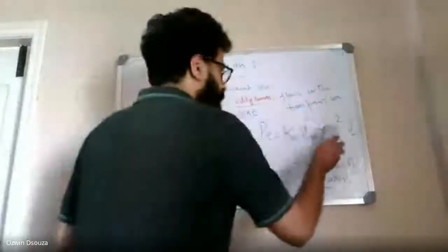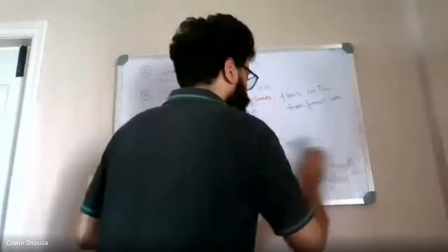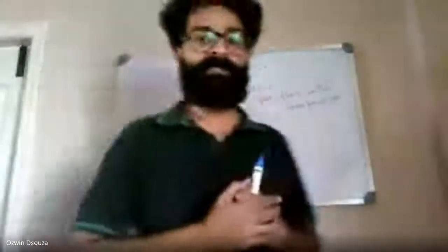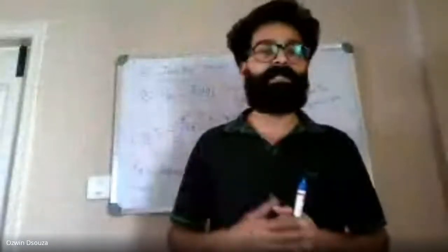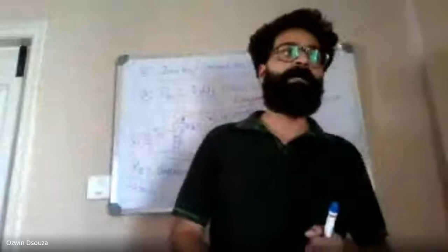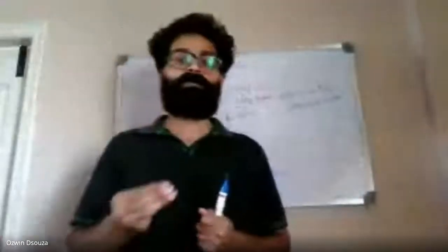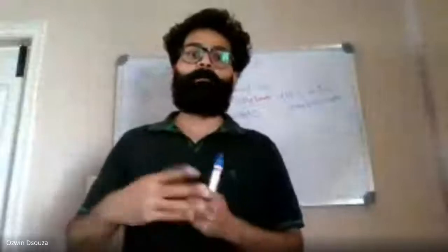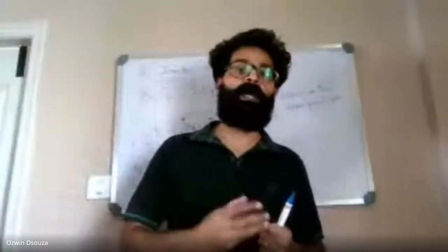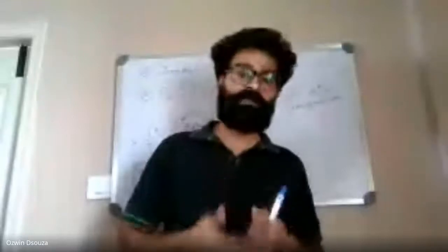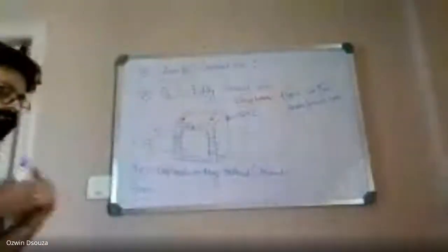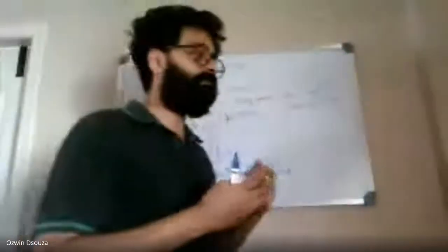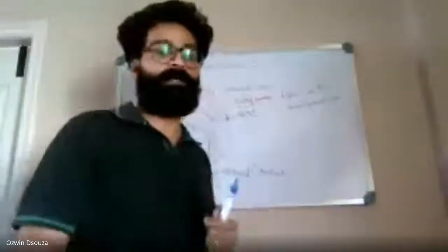Okay, fine. Now, how do you minimize the eddy current loss? Hysteresis loss, I have already told you. To minimize hysteresis loss, you have to select a magnetic material which has a very low hysteresis coefficient. For example, silicon steel has a hysteresis coefficient value of 0.001. On the other hand, cast steel has a hysteresis coefficient value of 0.025. So choose a magnetic material having a very low hysteresis coefficient value. Or you simply go for a magnetic material which has a very high relative permeability.